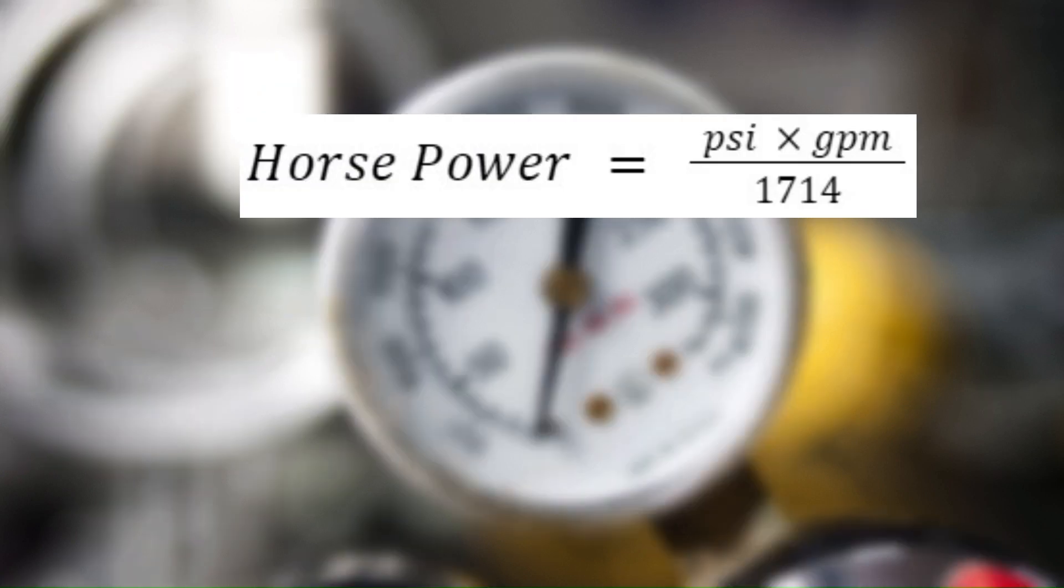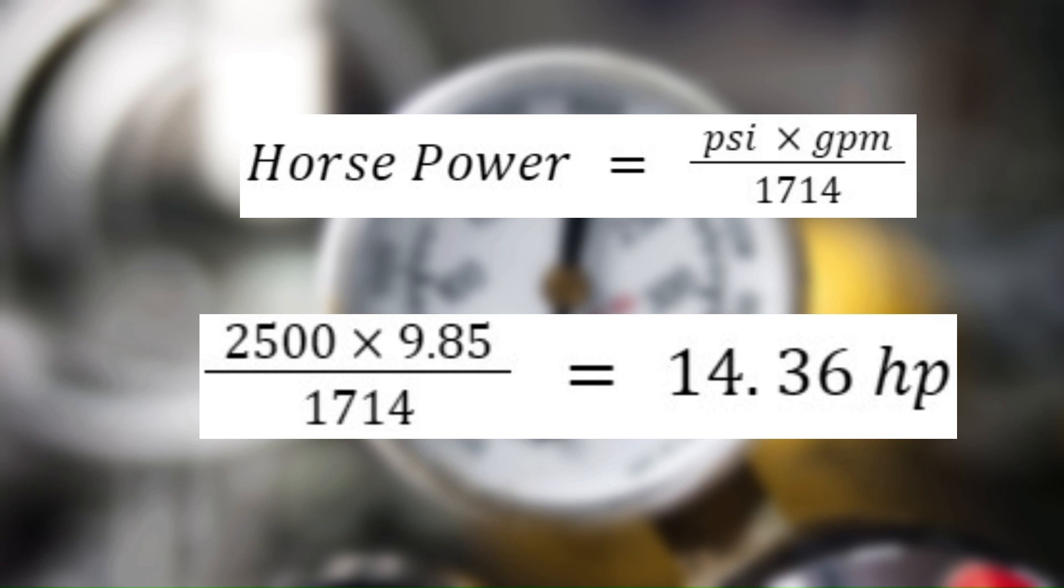We can now use this equation to calculate the required horsepower to run the pump. Doing this math, we get 14.36 horsepower. Since motors don't come in the 14.36 horsepower size, we would round up to a 15 horsepower motor.